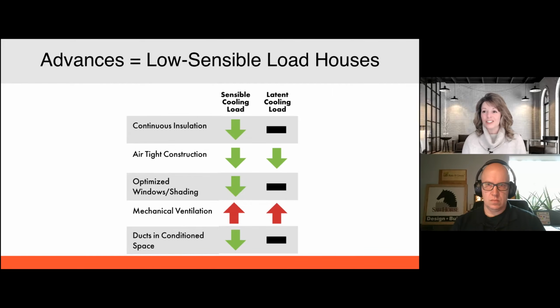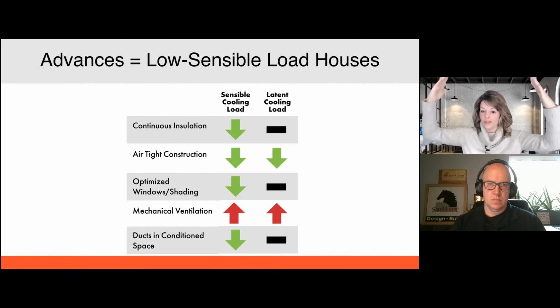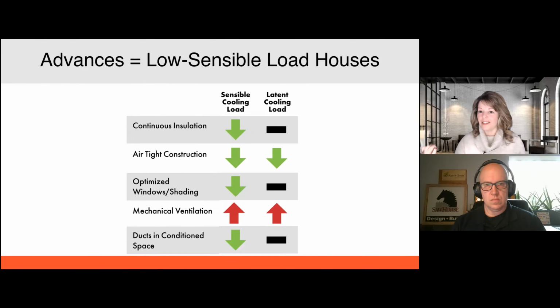Now, ducts in conditioned attics is driving down our sensible cooling because we're not losing that conditioned air outside of the envelope anymore. We've changed the envelope to the roof line, and we're keeping whatever we're losing through our ductwork in the house. And you know, this chart's showing that that's not affecting our latent cooling, but the reality is when we lost that conditioned air out into the open with our unconditioned attics, our air conditioners ran a lot longer, which also meant we got more moisture removal as a result of that.